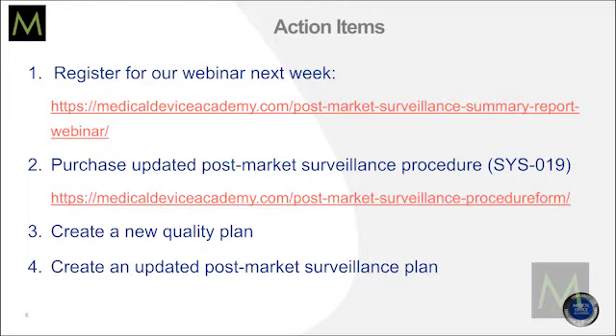Whenever you're making a change to a quality system, you're typically expected to have a quality plan. The FDA is very vague on this — some people say their quality manual is their quality plan. That's not really what they meant in ISO 13485. What they meant is a step-by-step with milestones and who is responsible: what changes are you going to make, who's going to revise the procedure, who's going to review it, when are you doing an internal audit to make sure the new procedure is effective, who's going to train the people, and when do they need training by? That's what belongs in a quality plan.